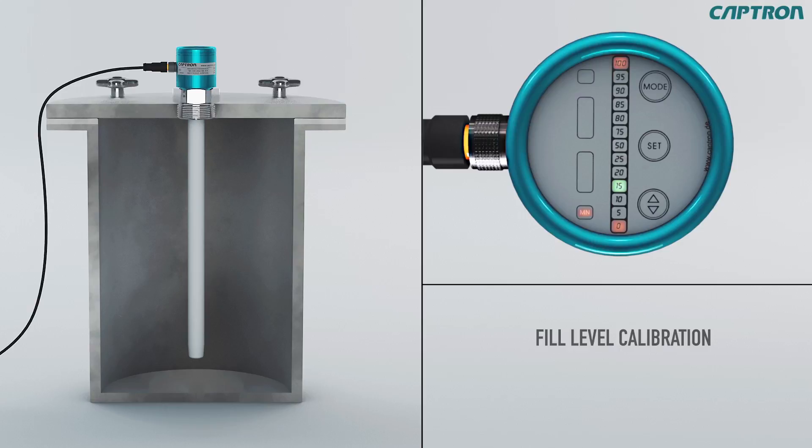Fill the tank with 5 to 25% of the desired measurement range. Now with up-down, you can set the value which corresponds to the actual fill level. Then confirm the value with set. After 5 seconds, the probe will jump to the next step.